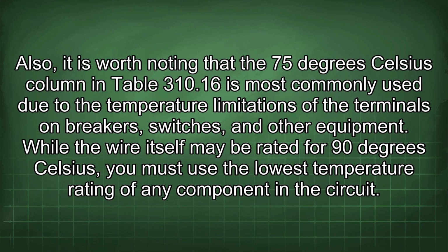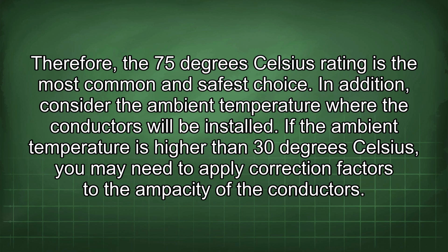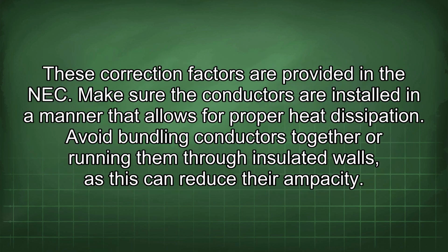Also, it is worth noting that the 75 degrees Celsius column in Table 310.16 is most commonly used due to the temperature limitations of the terminals on breakers, switches, and other equipment. While the wire itself may be rated for 90 degrees Celsius, you must use the lowest temperature rating of any component in the circuit. Therefore, the 75 degrees Celsius rating is the most common and safest choice. In addition, consider the ambient temperature where the conductors will be installed. If the ambient temperature is higher than 30 degrees Celsius, you may need to apply correction factors to the ampacity of the conductors. These correction factors are provided in the NEC. Make sure the conductors are installed in a manner that allows for proper heat dissipation. Avoid bundling conductors together or running them through insulated walls, as this can reduce their ampacity.